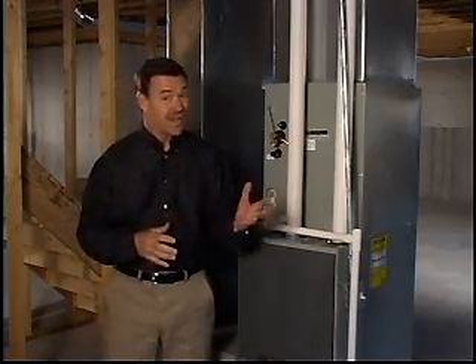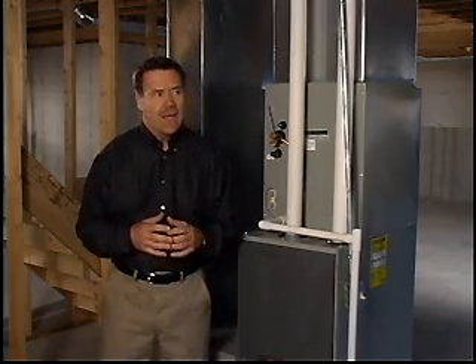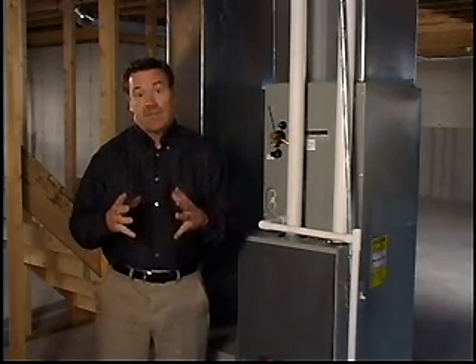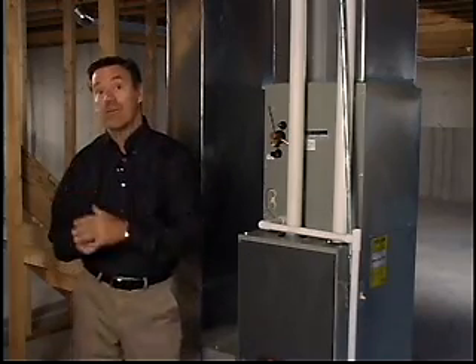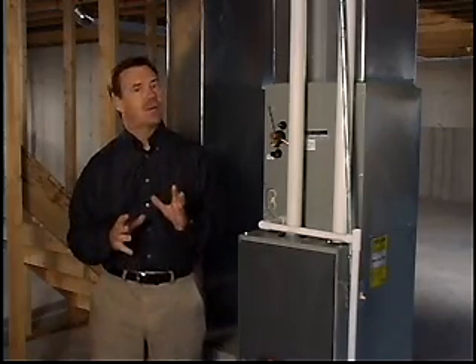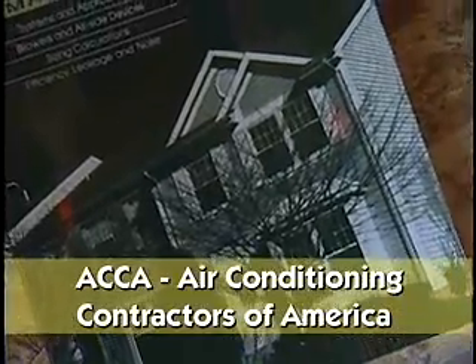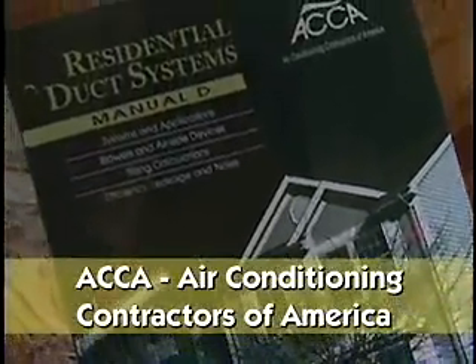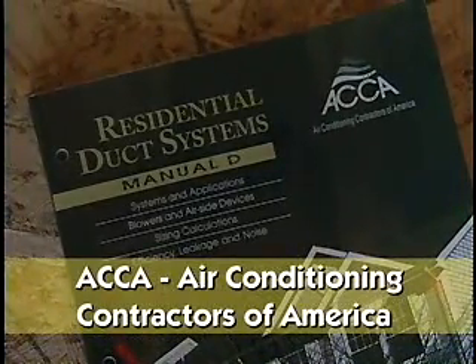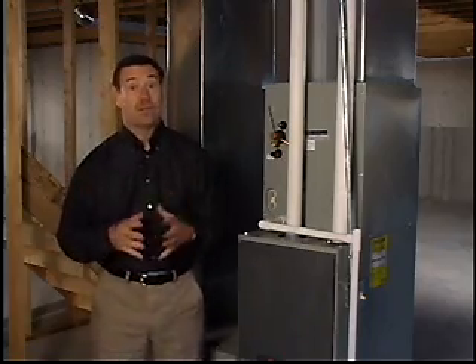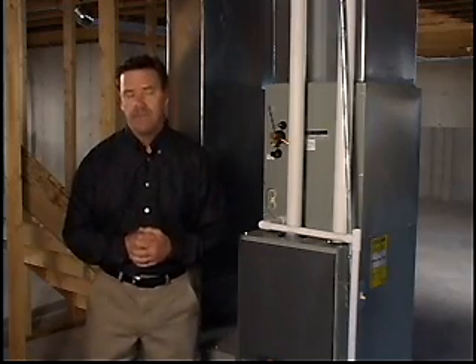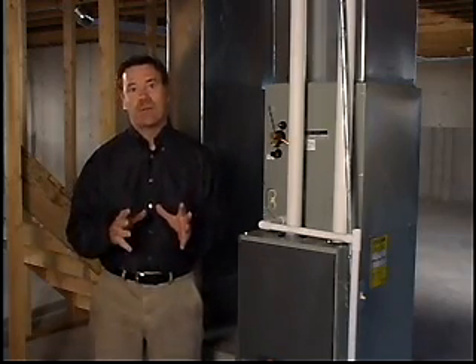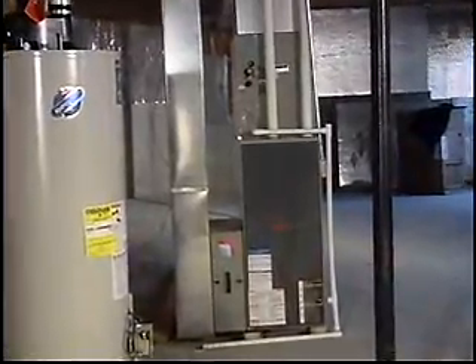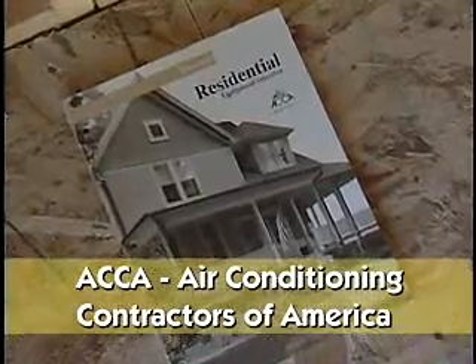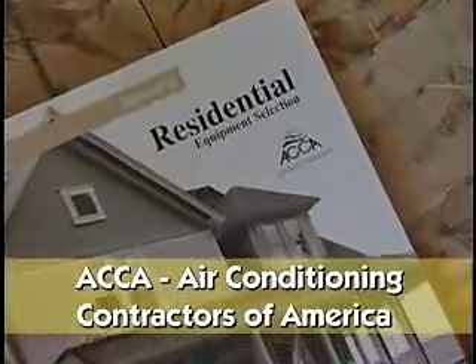Also, ductwork itself tends to be undersized. We tend to oversize air conditioning systems and undersize ductwork. And what basically happens is that we don't get enough space in the ductwork to adequately get airflow through the system. So what we want to be able to do is design our ductwork according to ACCA Manual D. That way we're sure not to have excessive friction loss that impedes the flow of air through the ducts, because to condition air we have to be able to move it through ducts and get it to the conditioned spaces that we want to heat or cool. Also, it's important to understand that we need to select the equipment according to ACCA Manual S. That helps us select the right equipment for the right job.